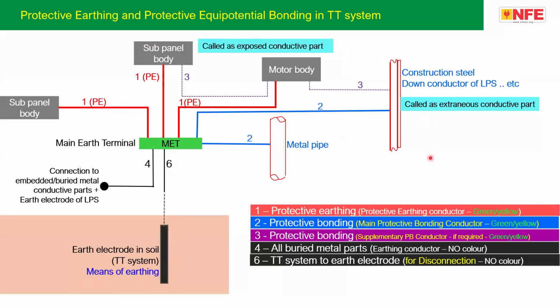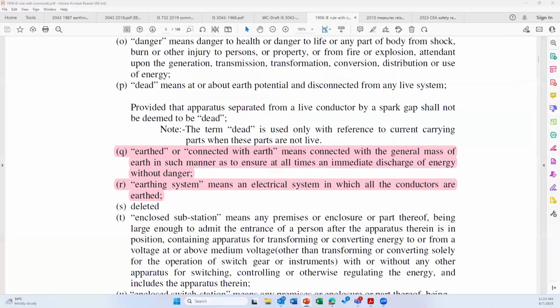The meaning is, in a TT system, this earth electrode is the sole means of earthing. It means the entire fault current is supposed to flow through this earth electrode in soil. Gas pipes shall not be used as a sole means of earthing means you should not use the buried gas pipe so that the fault current flows through it. But of course, the metal pipe, you must bond it. So these changes basically have made very big changes in the entire system.